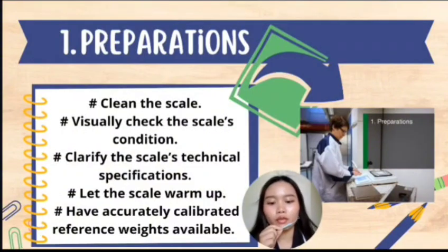First, we should clean the weighing platform thoroughly to remove dust, debris, or residues that could interfere with the readings. Second, we should visually check the scale's condition, whether it is broken or not. Then clarify the scale's technical specification, turn on the weighing scale and let it warm up for the recommended time, typically 15 or 30 minutes. This step will help stabilize the internal components. The last thing is to have an accurately calibrated reference weight available, which is to refer to the manual.